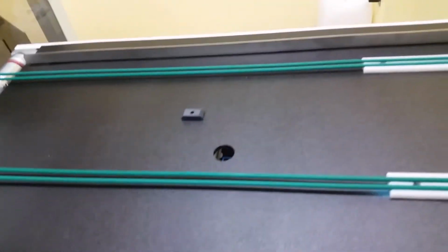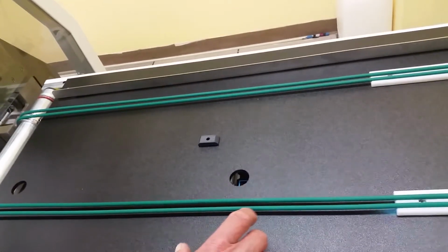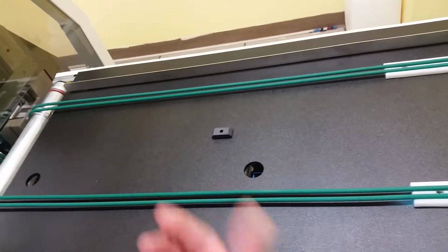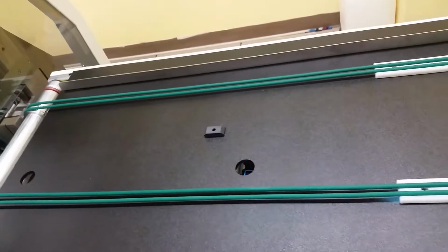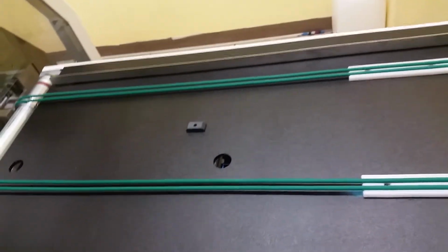So we've got photo eyes of some sort up here. That's your start eye back there, coming out of the processors. If a plate hits that, it's going to start this conveyor. Then it's going to use the length of the duration of time. If a plate passes over this sensor and it sees a break at the end of the plate, then it knows it's single. Now, if you get two single wides coming in on top of each other, it could think it's a double. Exactly.